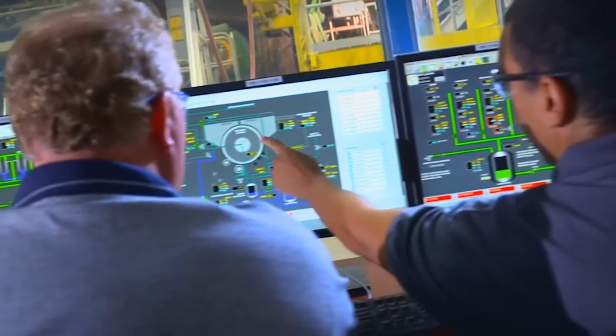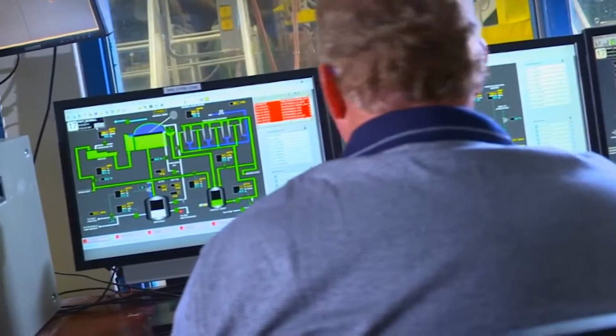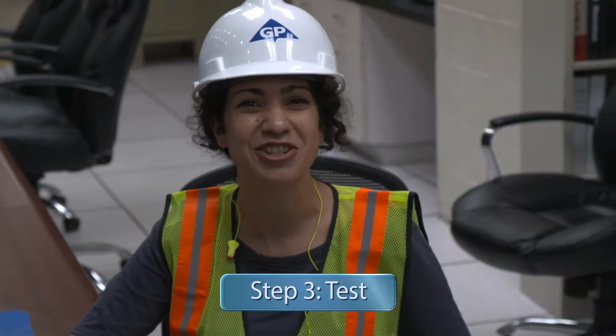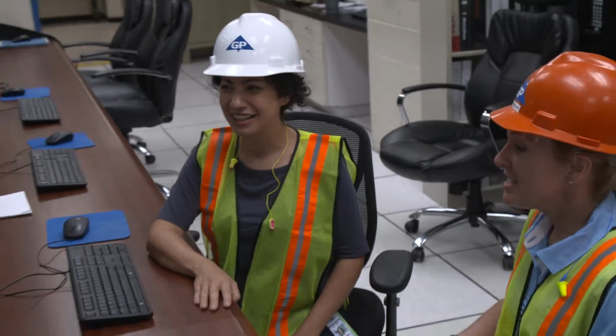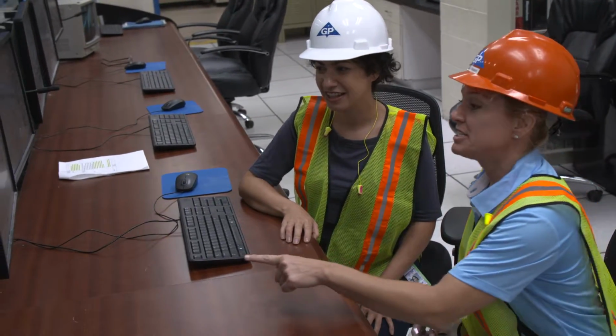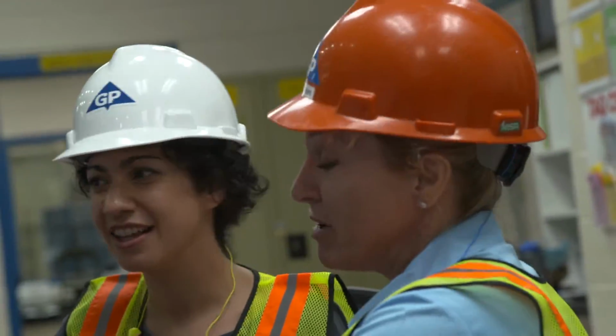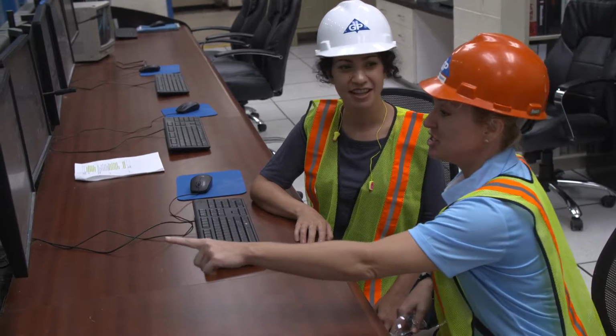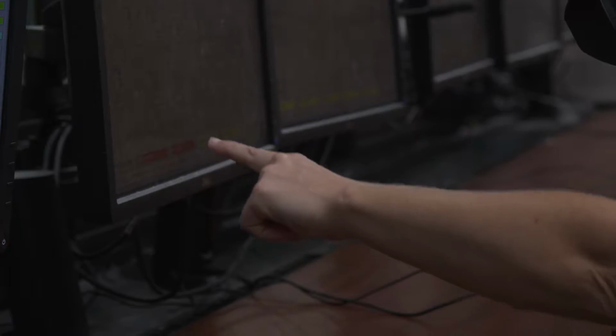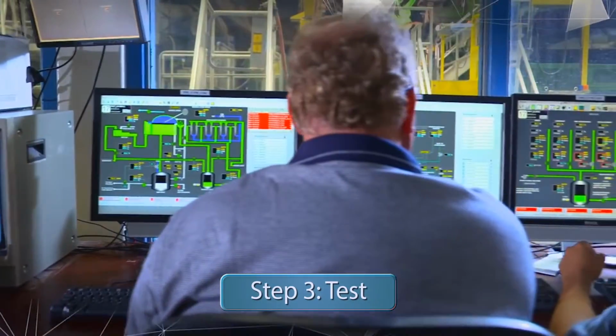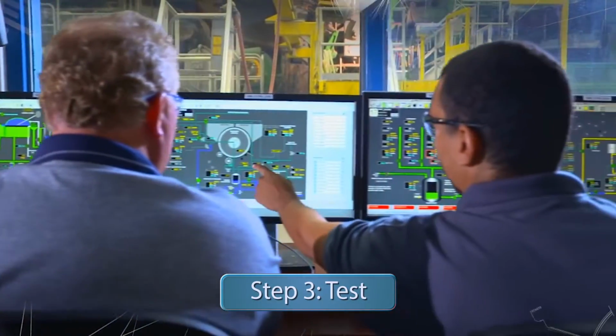We've engineered a solution to the temperature issues on paper machine 16 to keep it as reliable and productive as possible, and now it's time to put our engineering design to the test. So Renee, what do you think, is this going to work? Absolutely. Since we took the heat exchanger to the shop and discovered it had a tube leak, we've plugged the leak and reinstalled it, and as you can see here, the temperature has leveled out and is pretty stable.